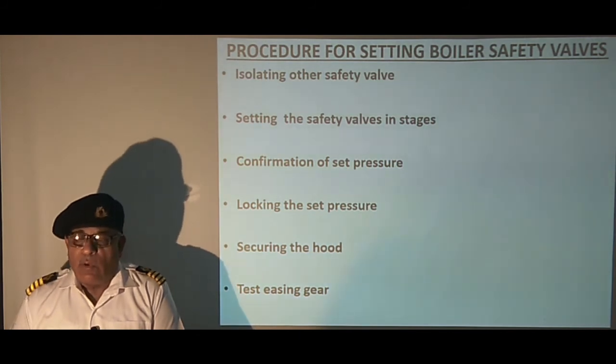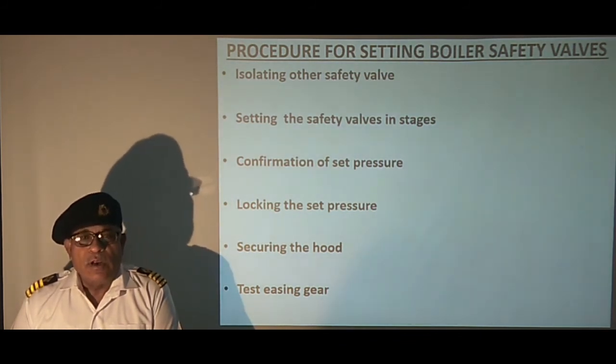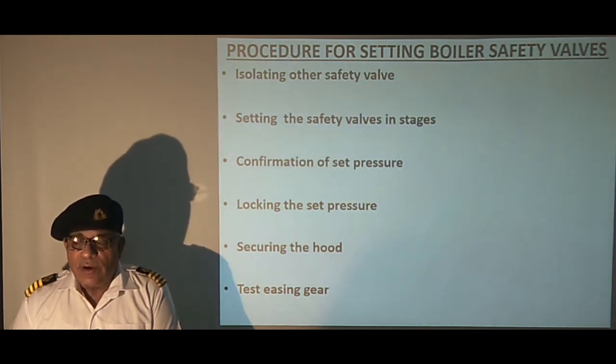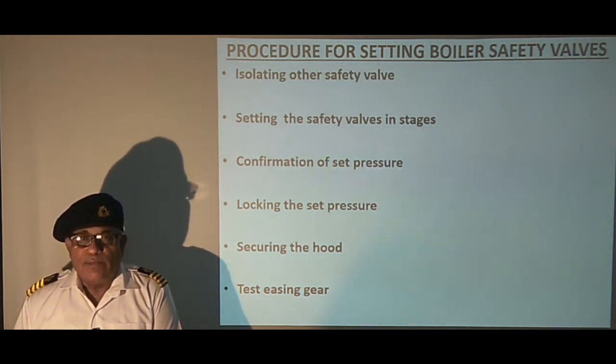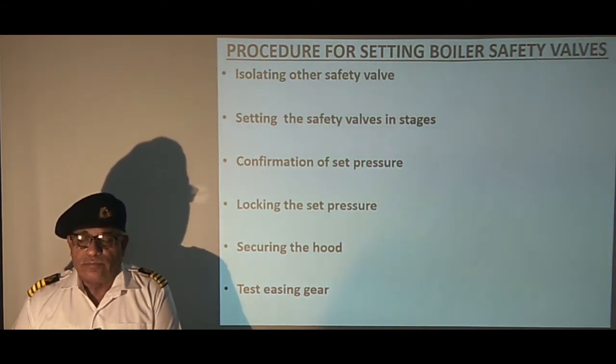The safety valve of waste heat boiler can be set once the vessel is at sea because it is operated when the ship sails out to sea. Chief engineer authorized by the classification society can set the safety valve. The information about the set blow off pressure and blow down should be conveyed to the surveyor for obtaining the credit for the survey. So that is the procedure of setting boiler safety valve.